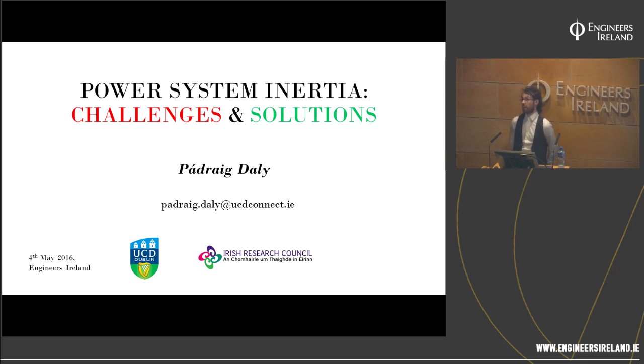Now, in England, I'm sure there are coal plants with quite high ratings, but in Ireland, we're only getting up to close to 400. So in comparison to a nuke at 1,000, it's not just your inertial constant that's important. People generally get hung up about inertial constants. It's the actual rated capacity of the generator as well.